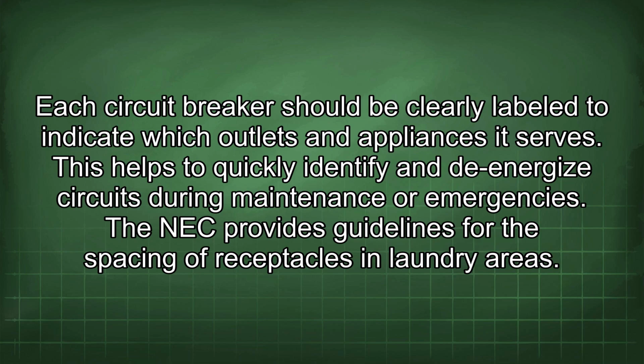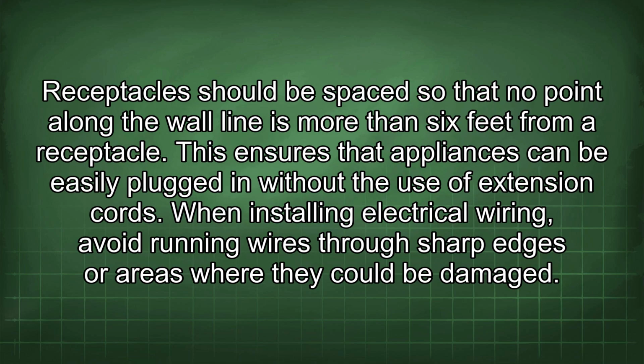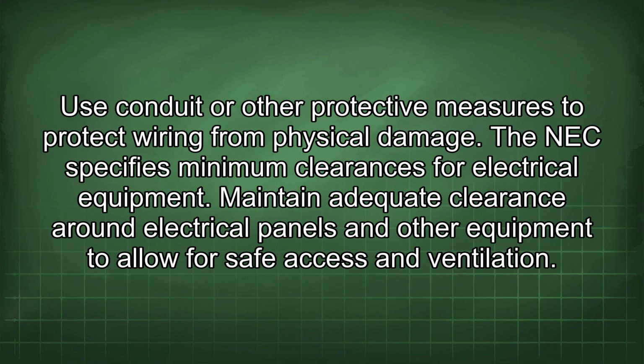The NEC provides guidelines for the spacing of receptacles in laundry areas. Receptacles should be spaced so that no point along the wall line is more than 6 feet from a receptacle. This ensures that appliances can be easily plugged in without the use of extension cords. When installing electrical wiring, avoid running wires through sharp edges or areas where they could be damaged. Use conduit or other protective measures to protect wiring from physical damage. The NEC specifies minimum clearances for electrical equipment.